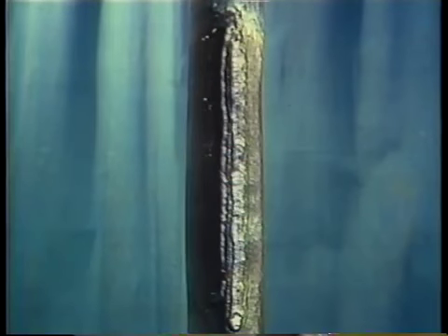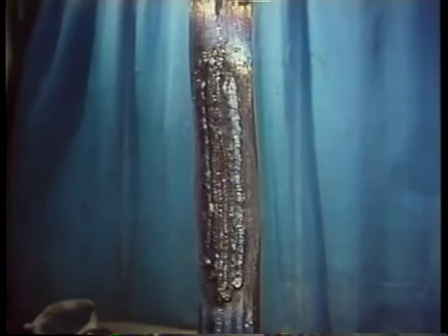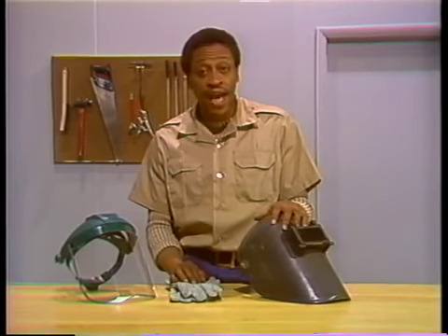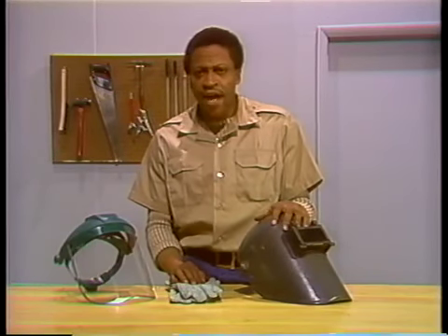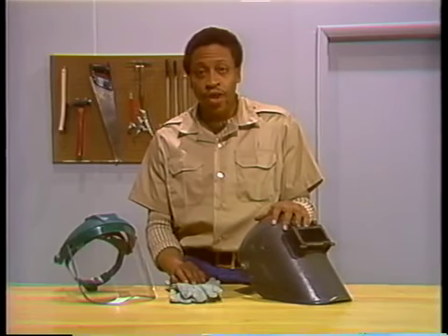The cladding is applied in the same way we showed you earlier and should extend well above and below the repaired area. After the repair is completely finished, the boiler will usually be hydrostatically tested. If a hydrostatic test is done, inspect the repair during the hydro to make sure it doesn't leak.